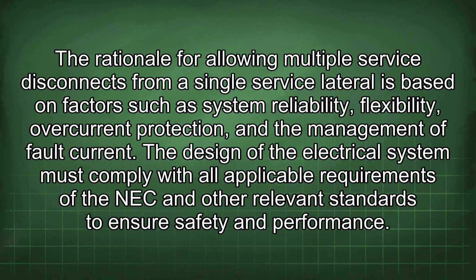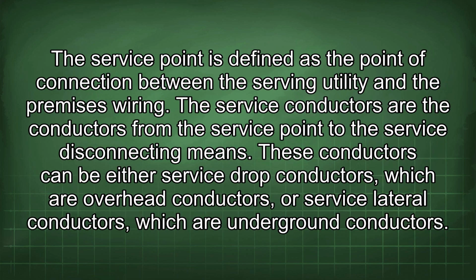The design of the electrical system must comply with all applicable requirements of the NEC and other relevant standards to ensure safety and performance. The service point is defined as the point of connection between the serving utility and the premises wiring. The service conductors are the conductors from the service point to the service disconnecting means. These conductors can be either service drop conductors, which are overhead conductors, or service lateral conductors, which are underground conductors.